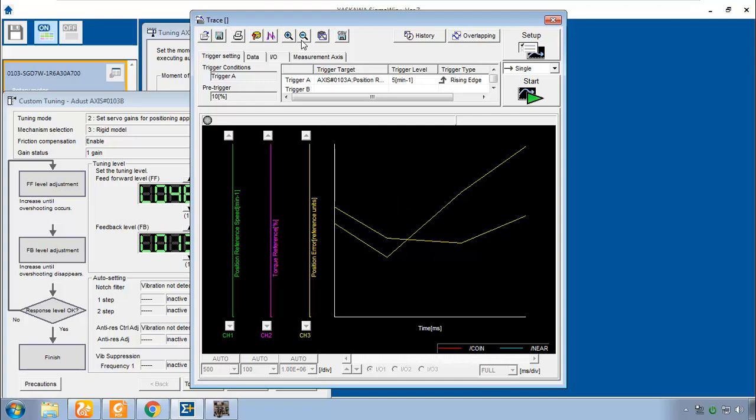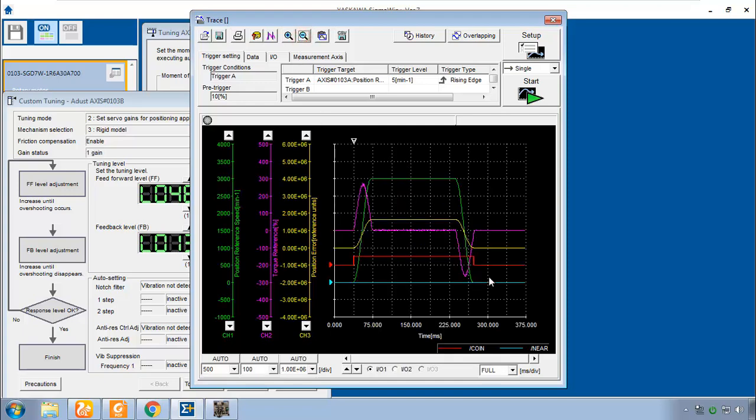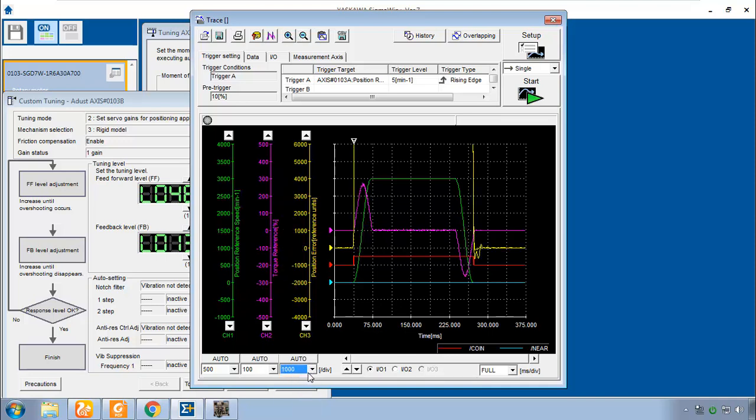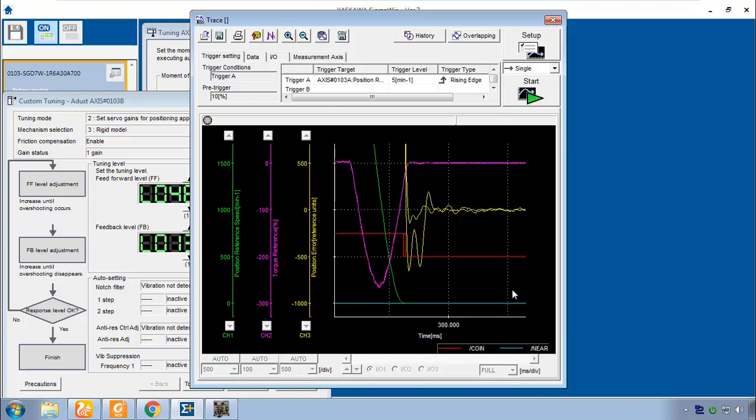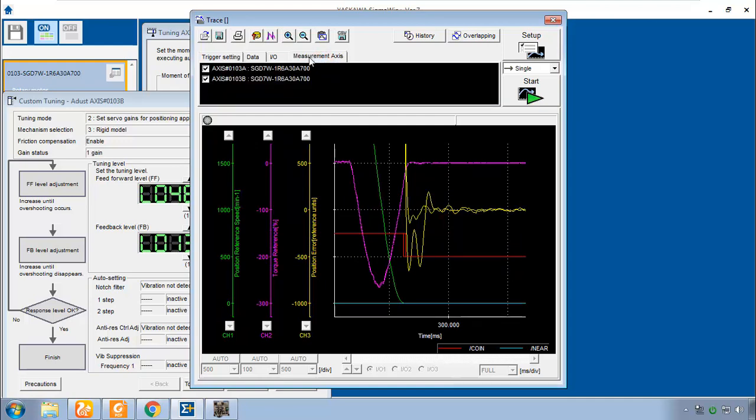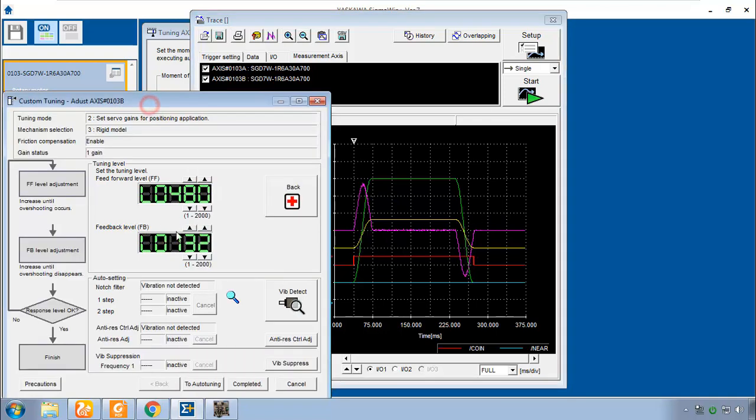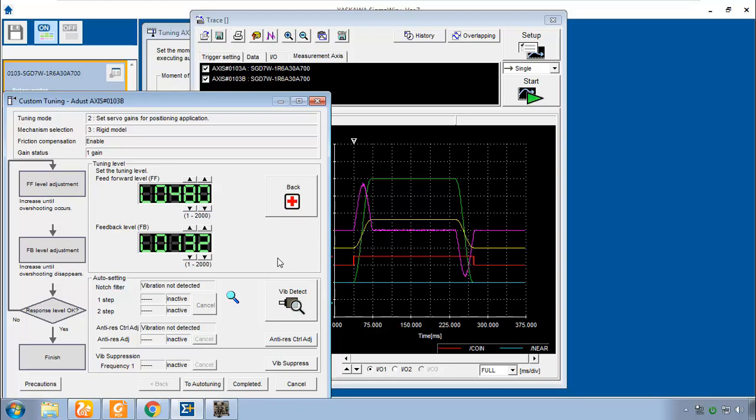And now we see that the response, particularly the position error, looks the same. We zoom in—it's for all practical purposes the same. And so these axes are in sync. Now the feedback levels are not the same between these two. So if we zoom in to the end of the move, just by changing the scale, you can see already how that is different. This is the B axis. If you're not sure about that, you can go to the measurement axis tab. The X axis is A, the B axis is Y. And so you see there is some difference between the two axes at move stop. However, it is only 500 encoder pulses of position error. That may or may not be acceptable, depends on your machine. So I'll leave you to do that on your own. I think you should be able to do it. You just set the feedback level to whatever you had for the X axis, and also the coin signal to 466. That was parameter PN522, and you may need a notch filter also. So why don't you pause it and see if you can do those three things on your own. Then I'll show you once again how I do it.